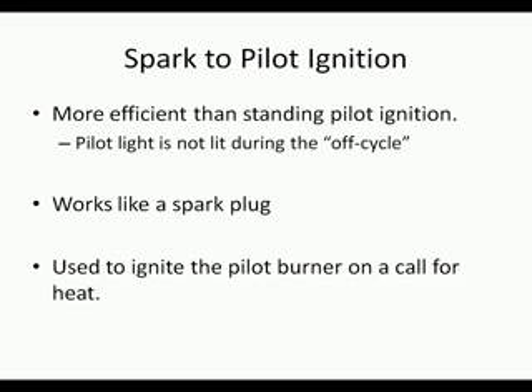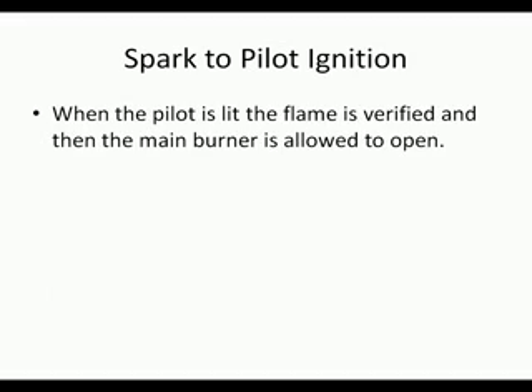You can also use an adapter on the end of the thermocouple lead. Again, now you're in parallel with the main gas valve. You should still be able to read 25 to 30 millivolts. The next type of ignition is the spark-to-pilot ignition. It's more efficient than the standing pilot because the pilot is not lit during the off cycle. It works like a spark plug. It's used to ignite the pilot burner on a call for heat.